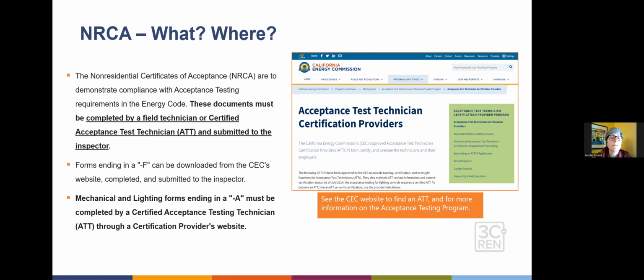Documents ending in A have to be completed by a field technician or certified acceptance technician and submitted to the inspector, and these all come back to the authority having jurisdiction. If it ends in A, it has to be the acceptance test technician, but some forms end in F, and those can be completed by a field technician, someone who isn't necessarily an ATT. Most forms for lighting and mechanical systems are going to require the ATT.